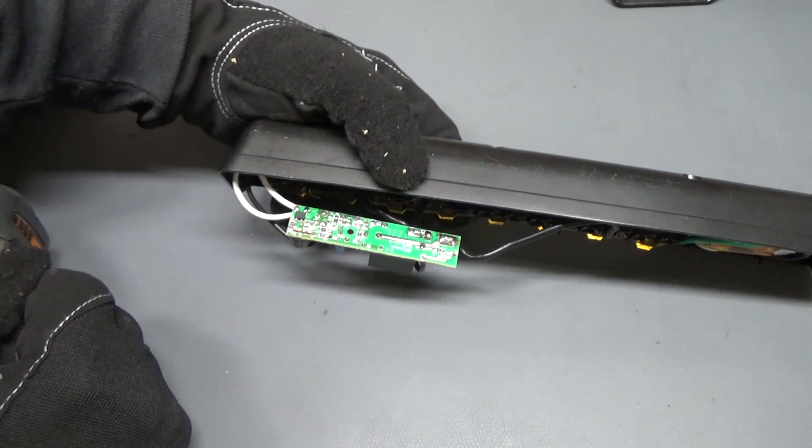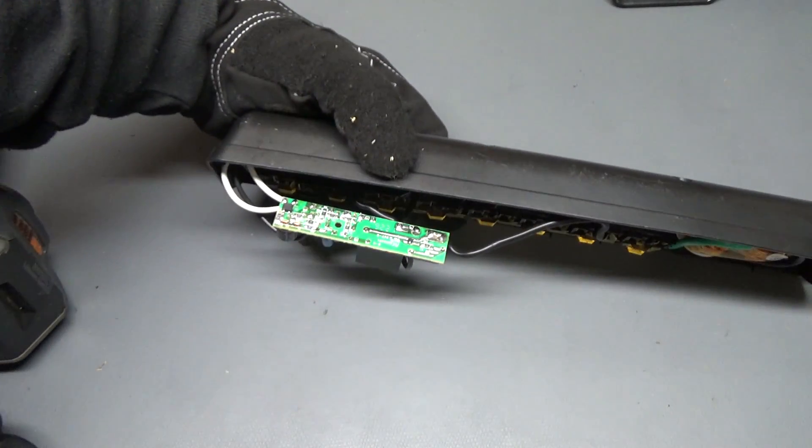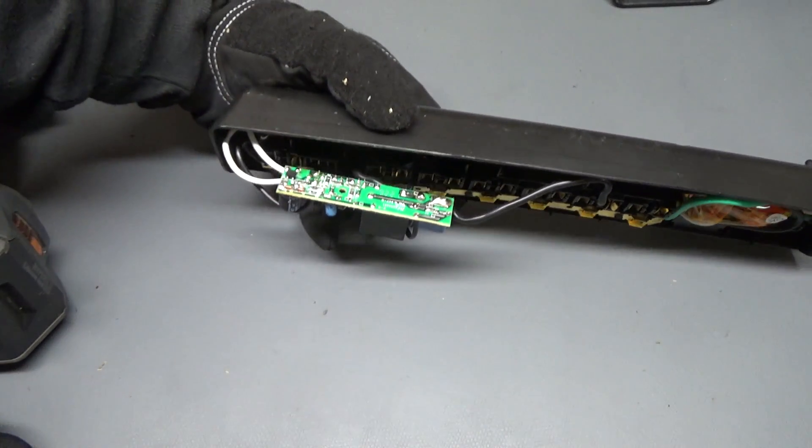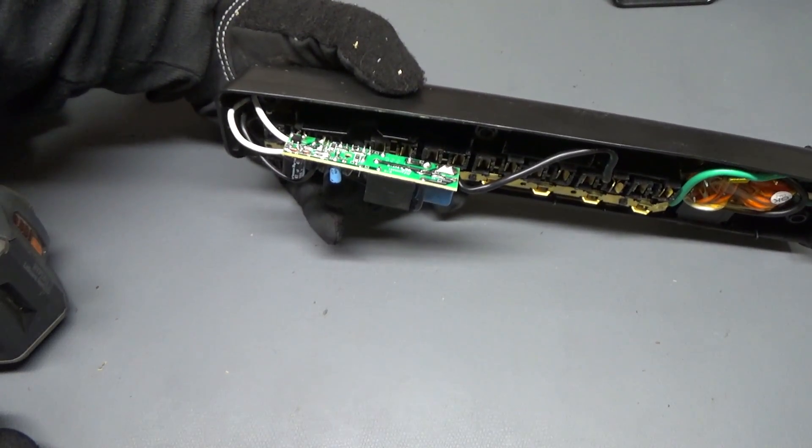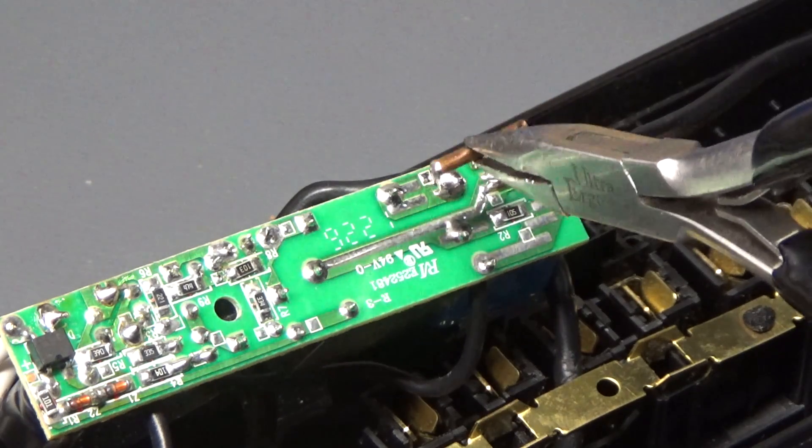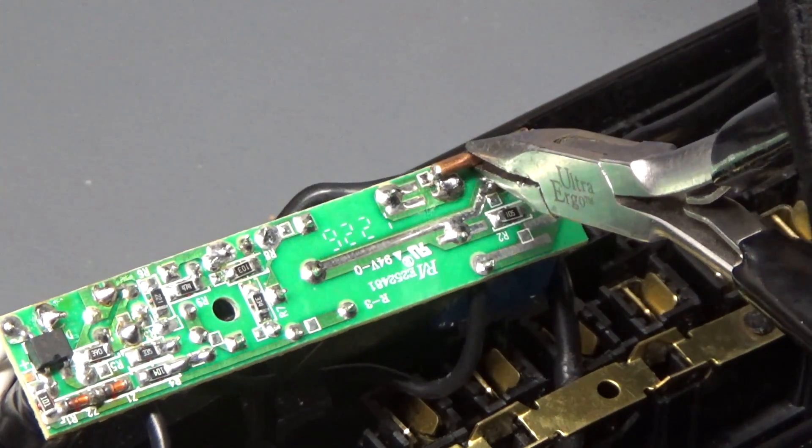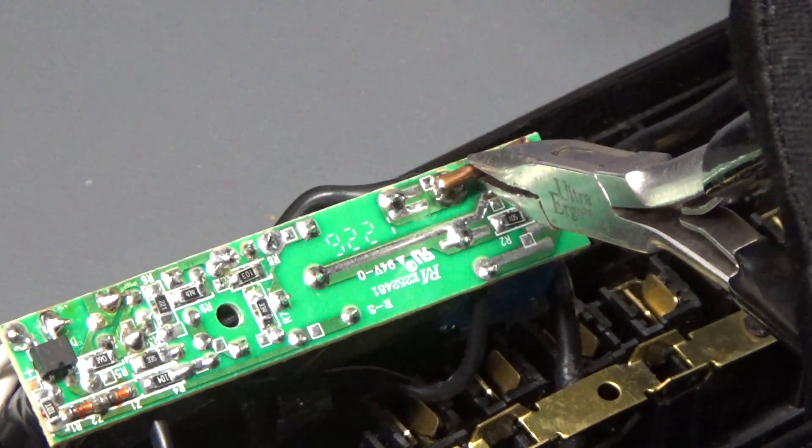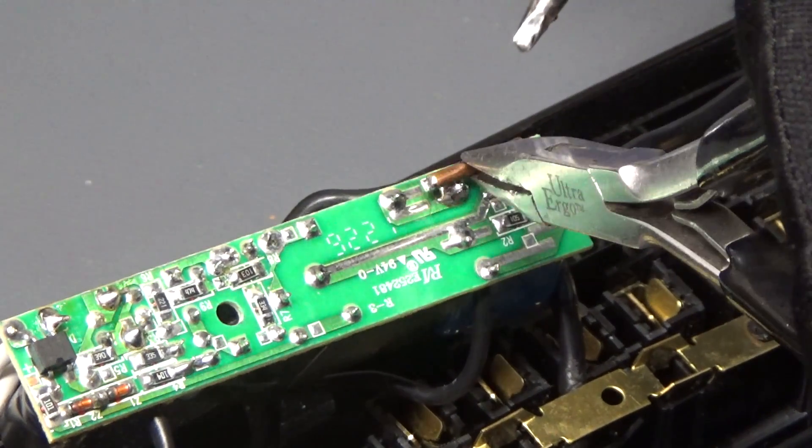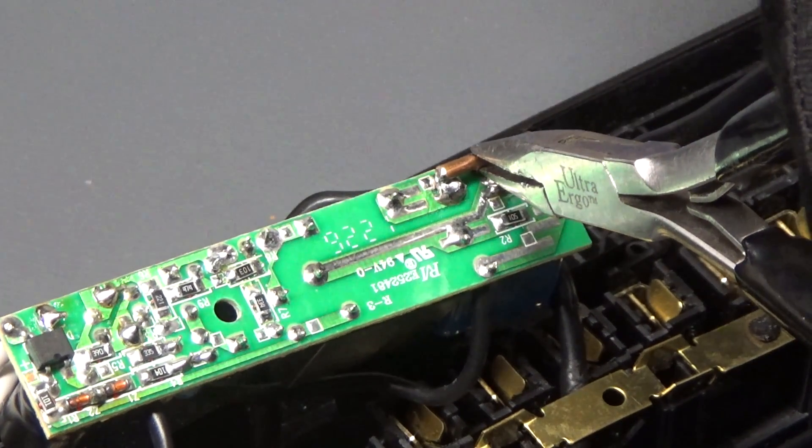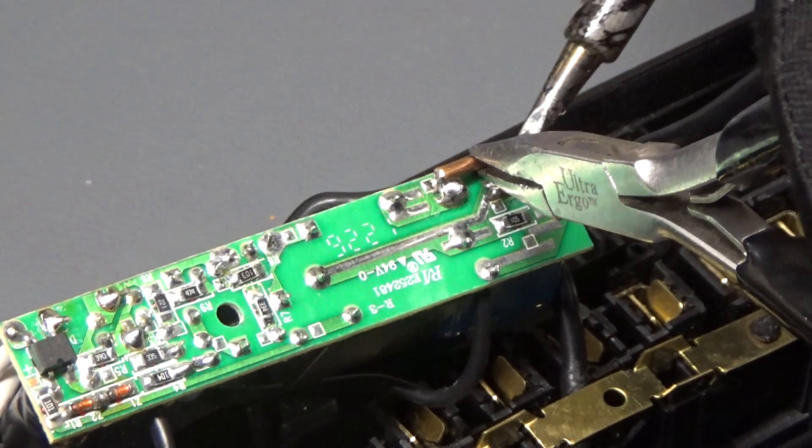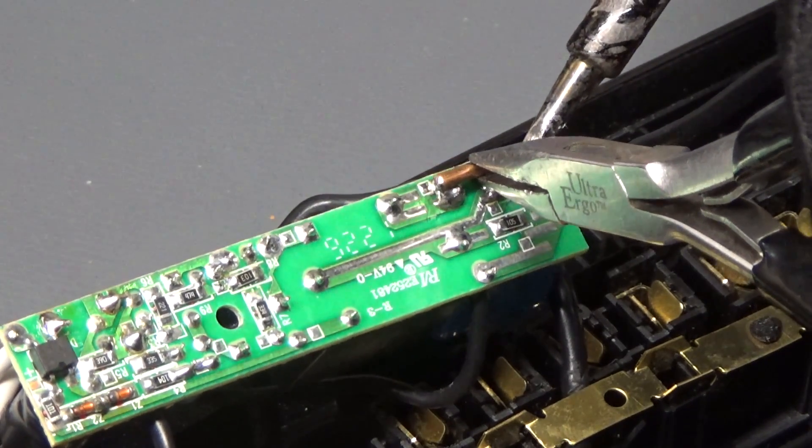So what we're going to do is bypass the relay so that the relay is always on. It doesn't matter what position the relay is in. So at this point, I'm going to be using 12-gauge copper wire, which is solid, to bridge the gap between hot and the normally open contact of the relay.